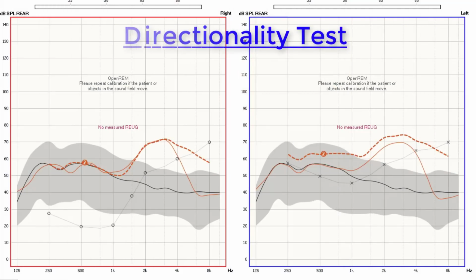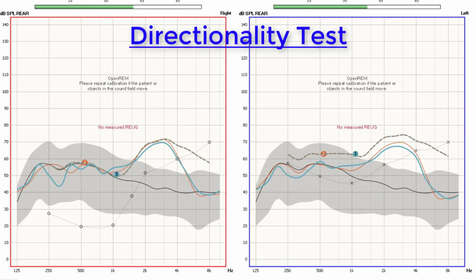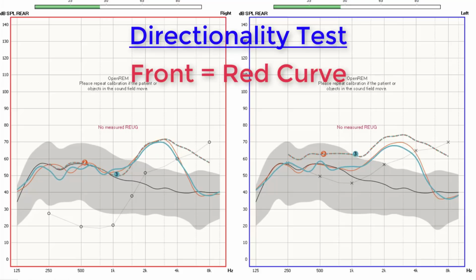Higher quality hearing aids do a substantially better job of reducing sounds from behind you and accentuating sounds from in front of you. This is called directionality, which is a feature that we can also objectively measure. When evaluating the directional microphone capabilities of a hearing aid, we compare amplification when sound is presented to the front of the hearing aid, which is illustrated by the red curve, to the amplification when sound is presented to the back of the hearing aid, which is illustrated by the turquoise curve.